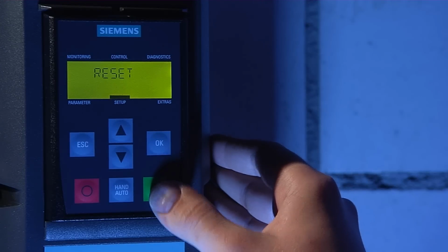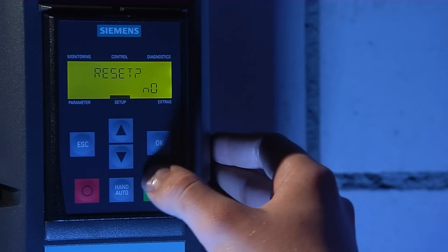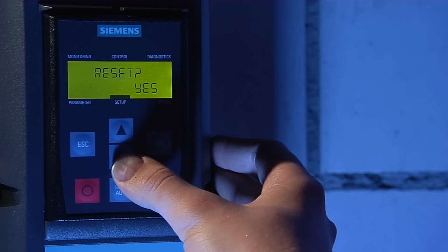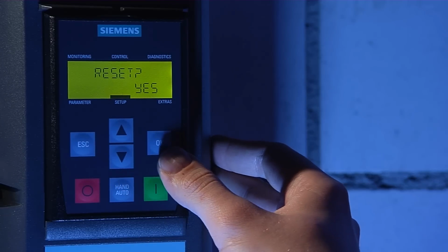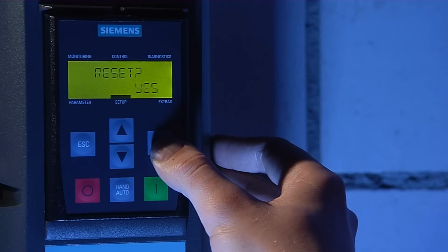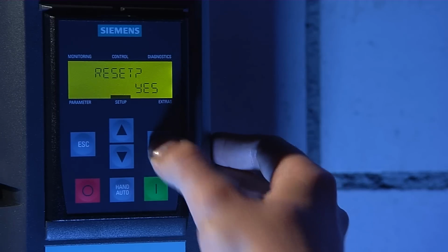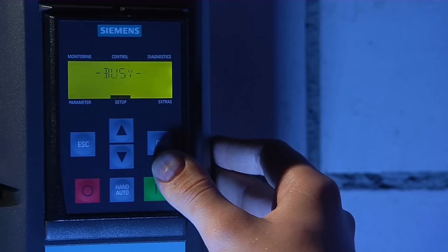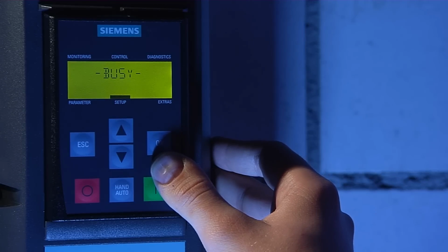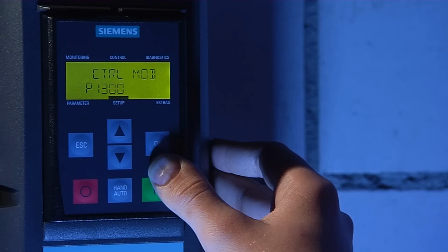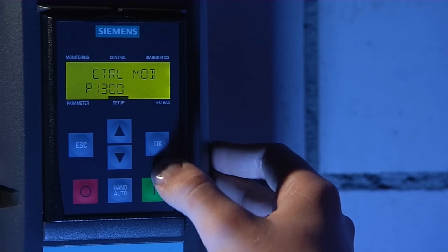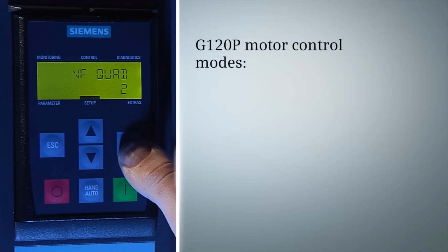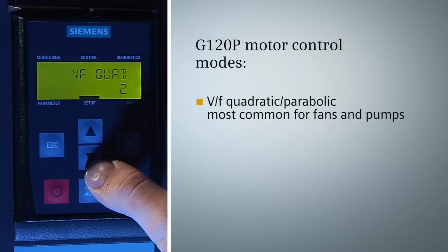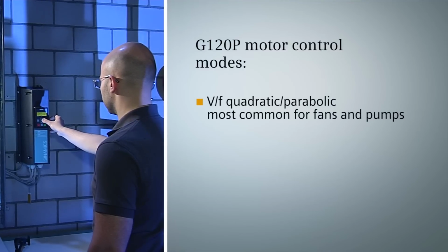This is recommended in order to ensure that the setup process starts with the basic settings. Press the button until Yes appears on the display and continue by pressing OK. The busy signal indicates that the drive is now restoring the factory settings. The next step is to select the control mode, which determines how the drive controls the motor. Confirm by pressing OK. The drive automatically defaults to V/f parabolic, the most common control mode in HVAC applications.